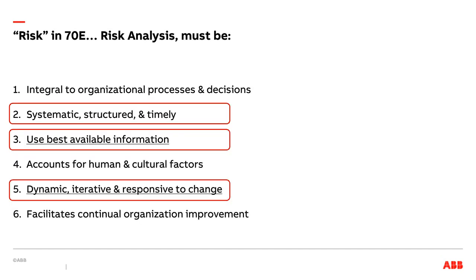It tells you, furthermore, that risk analysis needs to be systematic, structured, and timely. Then you need to use the best available information. And I think if somebody were to push you and say, well, I used the 2002 1584 method versus the 2018, and it's now 2020, I'm not quite sure how easy it would be to defend the position that you used the best possible information when you use the old method versus the new method. It tells you that risk analysis has to be dynamic, iterative, and responsive to change. Again, the way you calculate the science has actually changed.